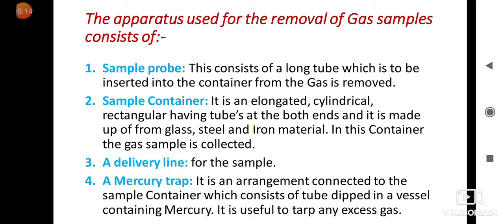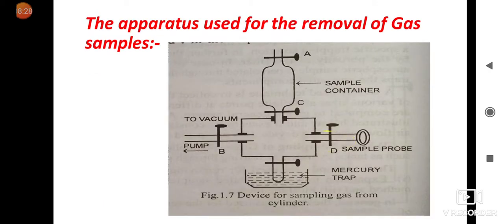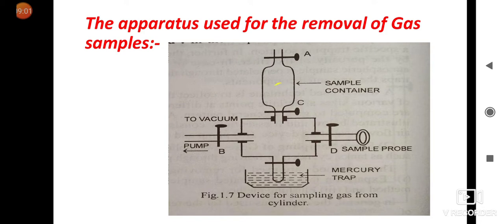The third term is the delivery line for the sample material. This is the part called the delivery line — it carries the sample from the sample probe going inside into the sample container. At that time, valves B and A are all closed, and whatever sample is coming from the delivery line through the sample probe is going into the sample container.